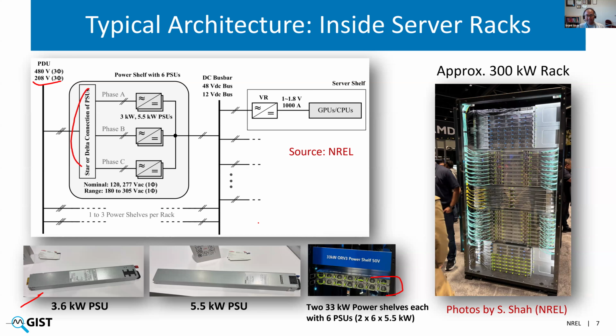And then they have an AC to DC conversion to a medium or middle level of 400 volt DC, and then a DC-DC converter to provide 48 volt output. The power rating of the PSUs is increasing: 3.6, 5.5 kilowatt, and now I also saw recently a 7.2 kilowatt PSU. The size of IT racks is growing. The biggest one that I saw recently is a 300 kilowatt rack, so a single rack consumes that much power. So this is a typical architecture, where we use 48 volt DC to supply IT racks, and the AC side is fed at 480 volts.